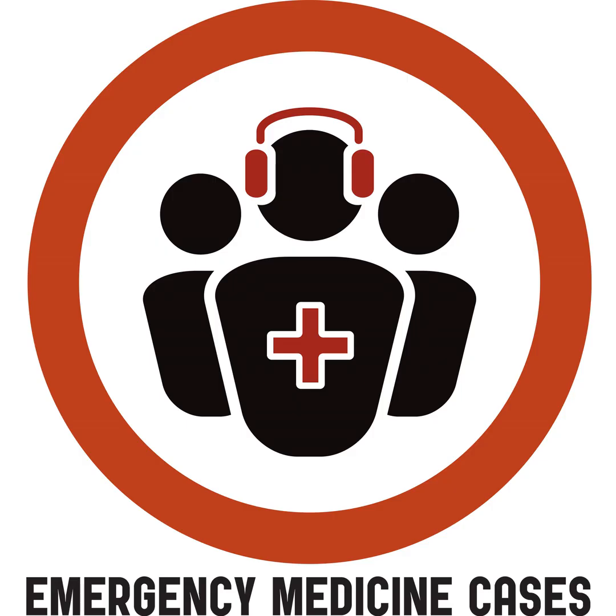A couple of other minor, but maybe not so minor points. You want to get electricity going across the heart. So you have to remember that your pads need to be put with the heart in between the pads. And we see this, of course, with cardioversion or defibrillation sometimes. When you see TV actors getting defibrillated or even, I don't know, not paced maybe, the right-sided pad is often just on the right side of the sternum and the left pad is on the anterior left sternum. The apical pad needs to be in the armpit, in the axilla. So you draw a line between the pads that goes through the heart. You have to be careful to make sure that the pads are really far apart.